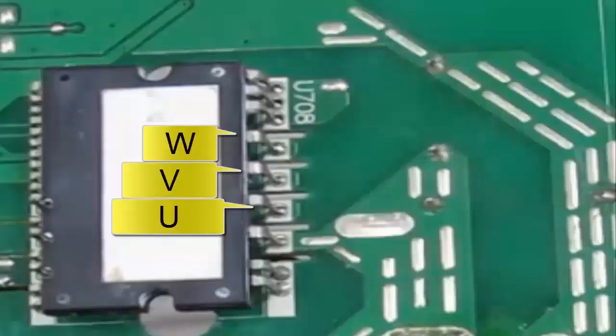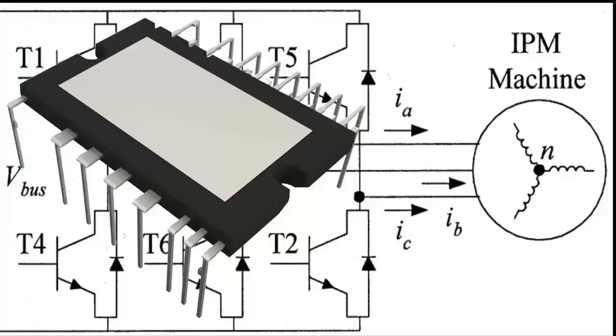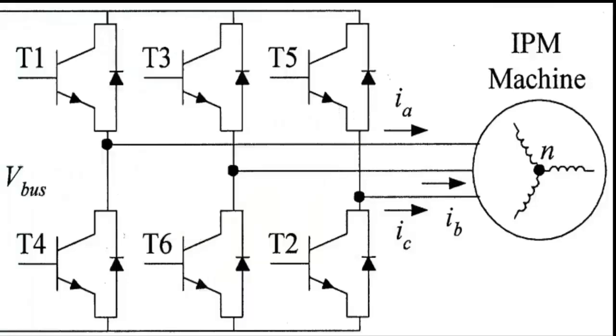Step 7: The IPM electronic circuit is internally composed of six IGBT transistors, each containing a diode that we will test. Let's start with the integrity test of the first three diodes.